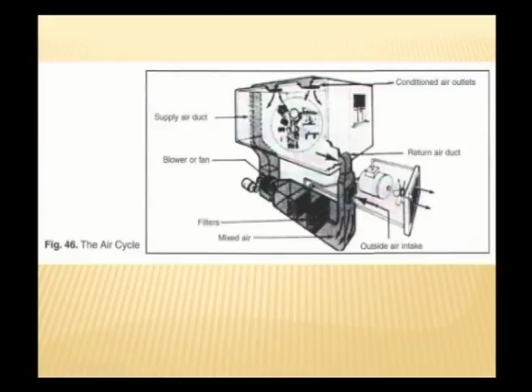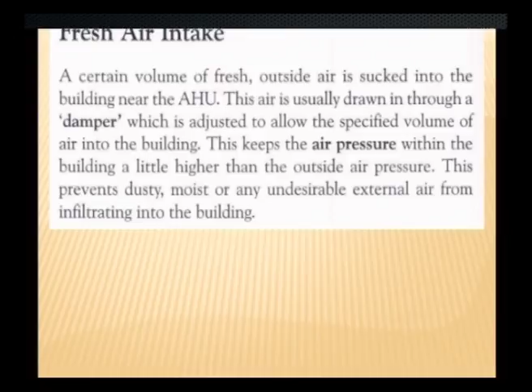Next comes the fresh air intake. A certain volume of fresh outside air is sucked into the building near the AHU. This air is usually drawn in through a damper, which is adjusted to allow the specified volume of air into the building. This keeps the air pressure within the building a little higher than the outside air pressure. This prevents dusty, moist or any undesirable external air from infiltrating into the building.